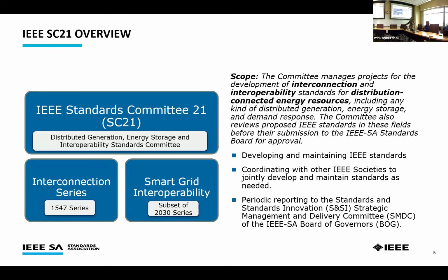The Standards Committee 21 focuses on two standard sets. 1547 addresses interconnection of distributed energy resources with the power system, essentially with the utility. Whatever your local utility is, they are likely using 1547 to set the minimum performance requirements. That's interconnection. The other set of standards is 2030, and that's interoperability.